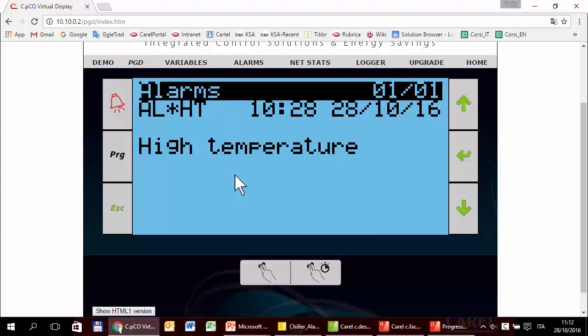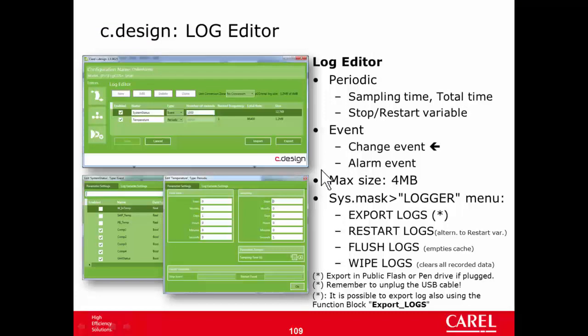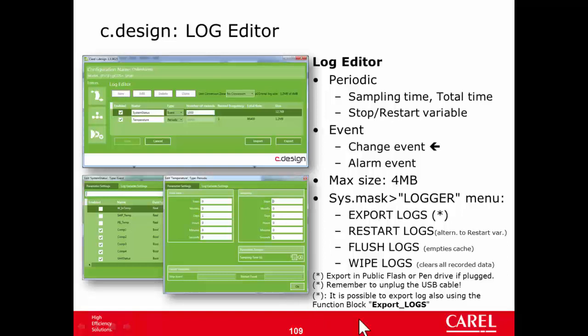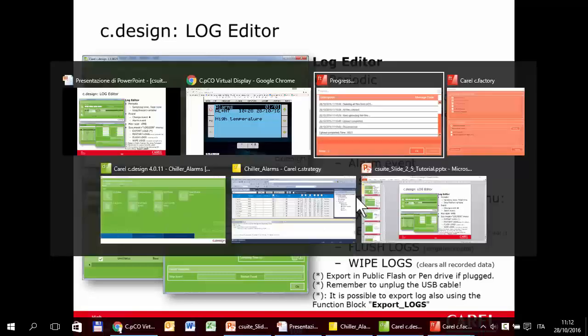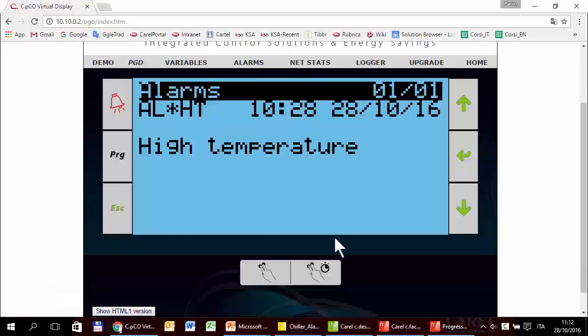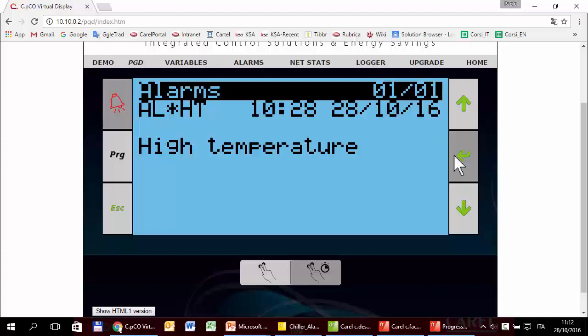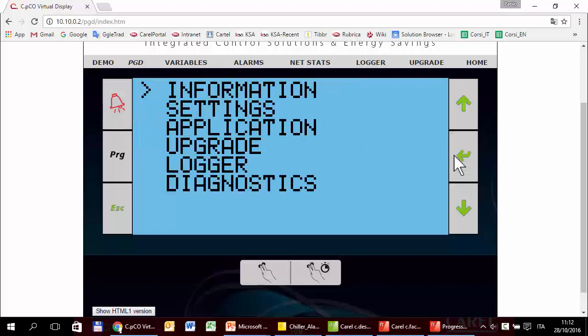Now we can see what the data logger has recorded. So how to export the logs. There are two options as usual. The first is using the system mask, system menu, logger. The second is using a specific function block. I will use the first option. First, export logs by system mask. So enter in the system menu. Alarm enter for two seconds. Logger.